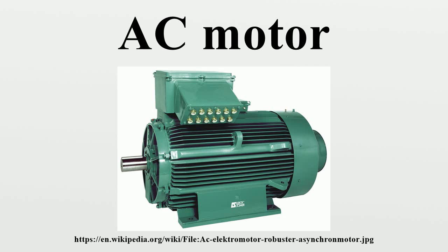Three-phase motors can be converted to PSC motors by making common two windings and connecting the third via a capacitor to act as a start winding. However, the power rating needs to be at least 50% larger than for a comparable single-phase motor due to an unused winding.